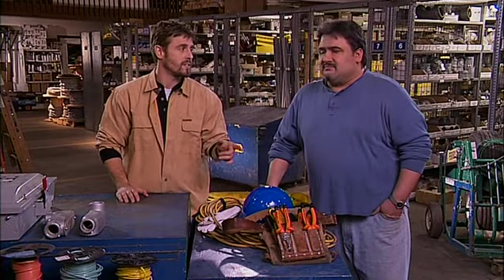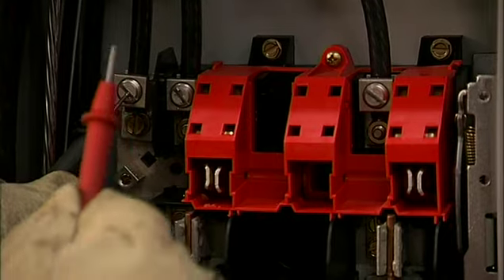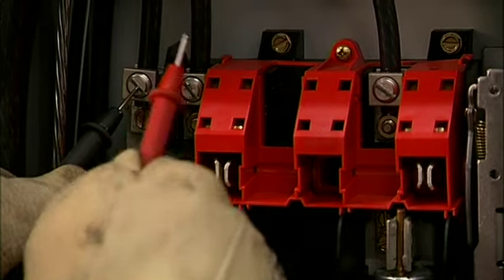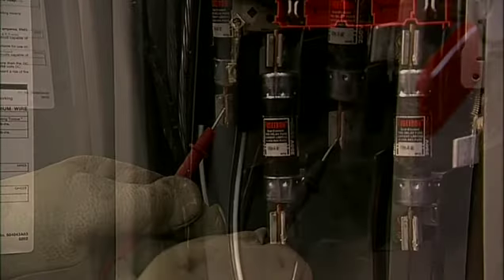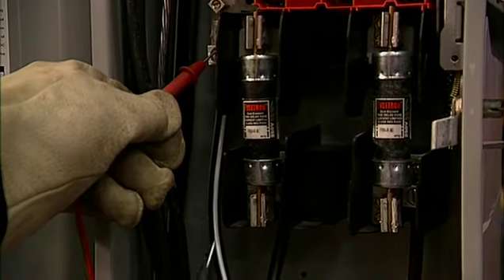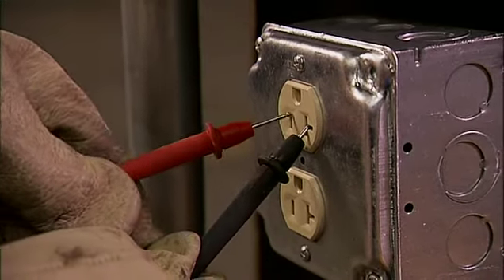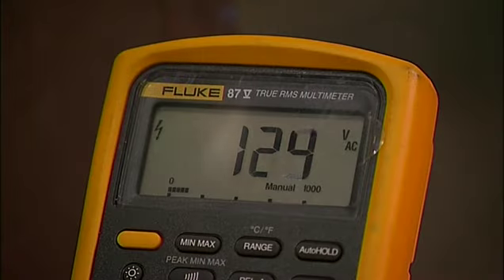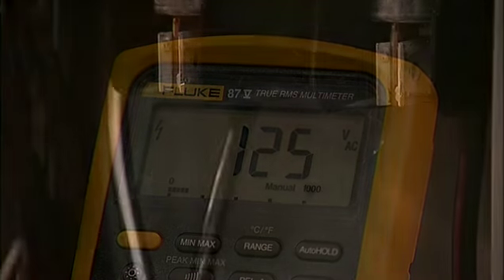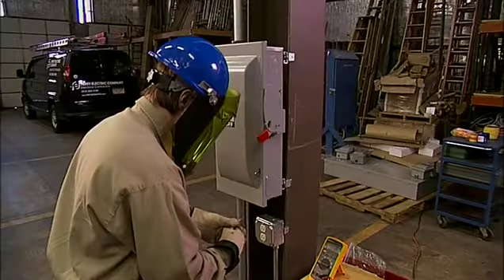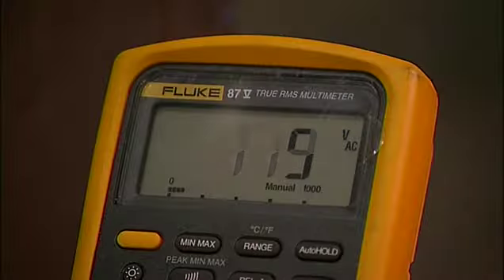So, what about testing the circuit? You need to test each phase conductor or circuit part to verify that they're de-energized. And you need to test them phase to phase and phase to ground. Before and after each test, determine that the voltage meter is operating satisfactorily. How's that? Test something you know the voltage of to make sure that the meter is operating correctly. Then, test the de-energized circuit, and then retest your meter. Got it. The important thing is to test for a known voltage before you start to work.